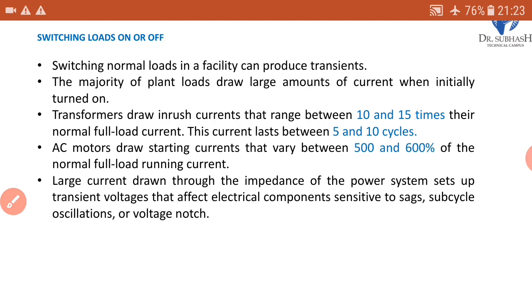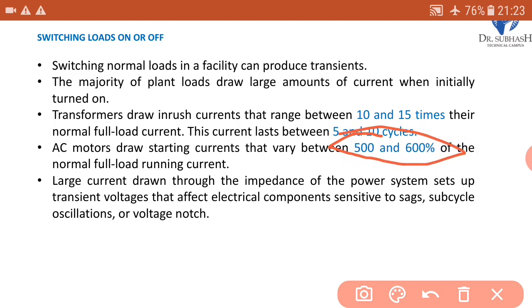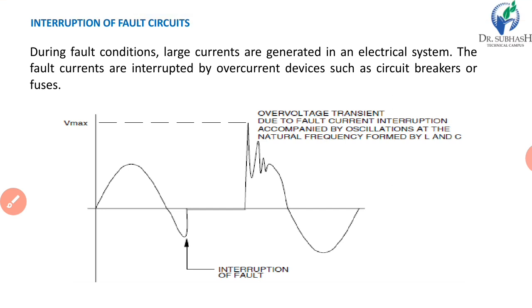Another one is that AC motors draw starting currents that vary between 500 to 600%. It means it is 5 to 6 times the normal full load running current. So this is also a very large current, and due to this a transient may be generated. Large current drawn through the impedance of the power system sets up transient voltages that affect electrical components sensitive to sag, subcycle oscillations or voltage notch. So these are the cases of switching loads on or off, and due to this a transient may be generated.